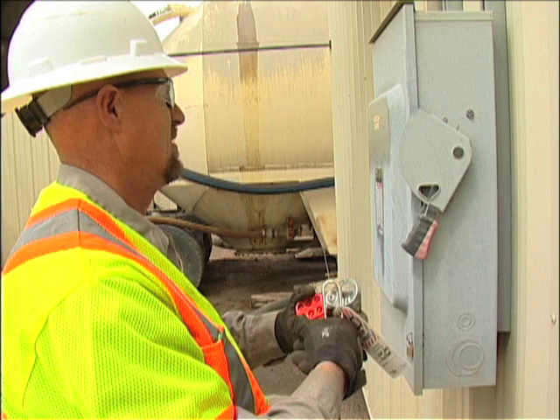There are certain times a lockout-tagout device may have to be removed without the employee being on site. The employer must verify the authorized employee who applied that device is not at the facility. The employer has made all reasonable efforts to contact the absentee employee. And when the authorized employee returns to the plant or facility, the employer informs the employee of removal of the device.